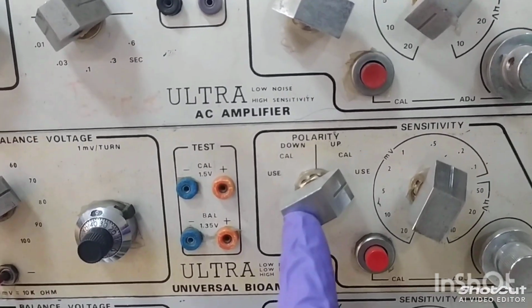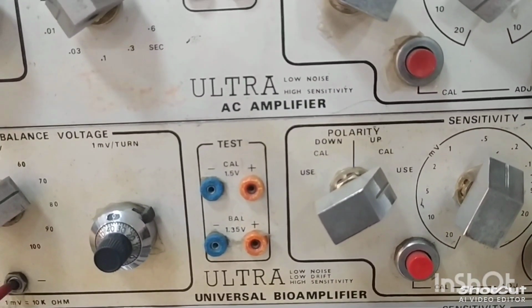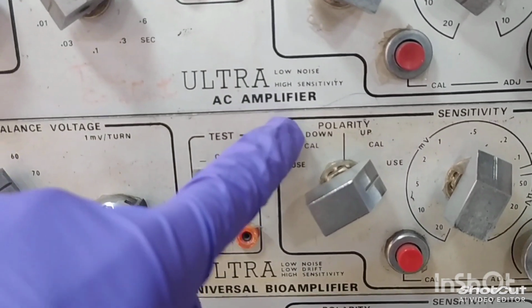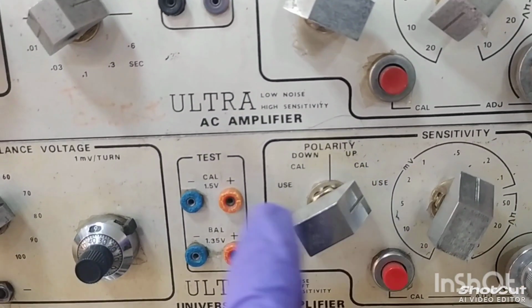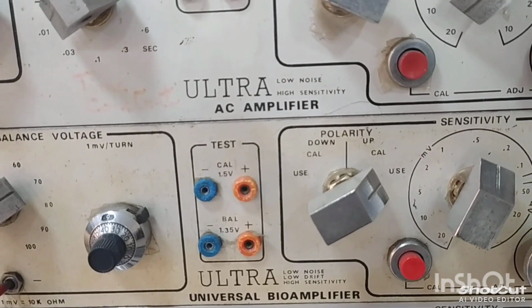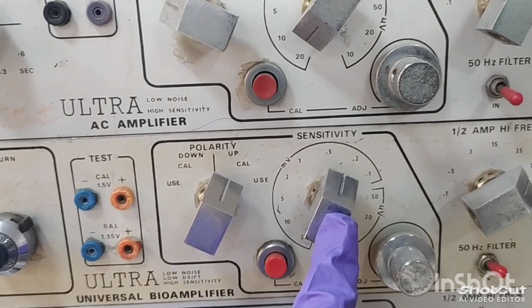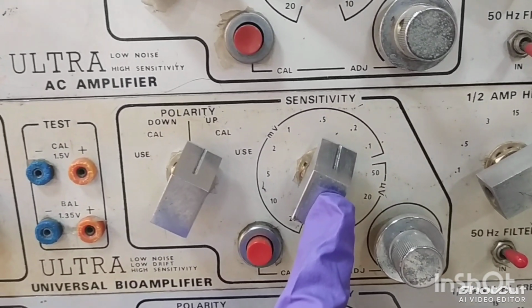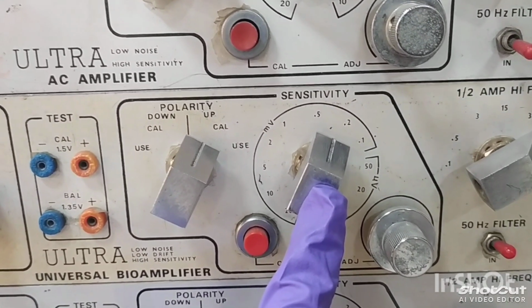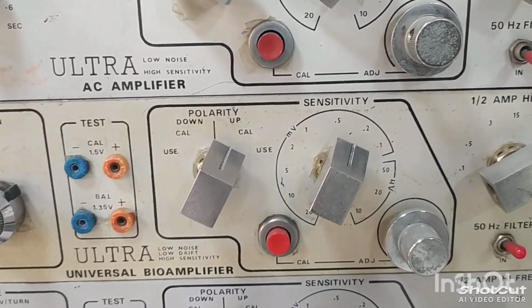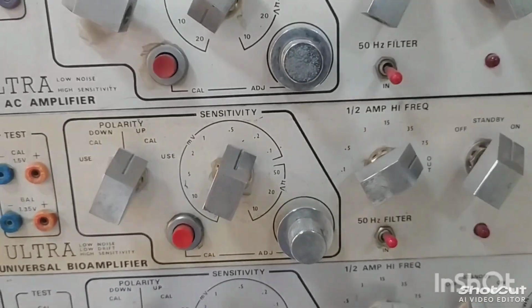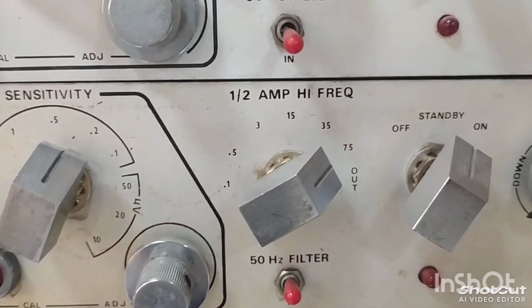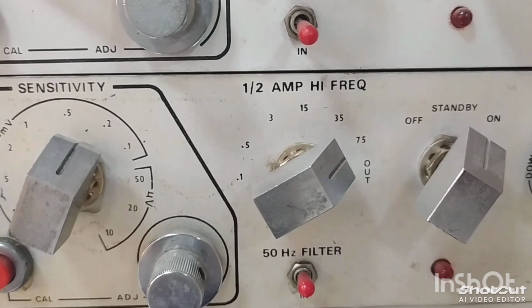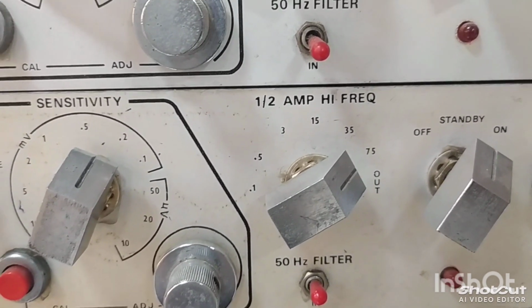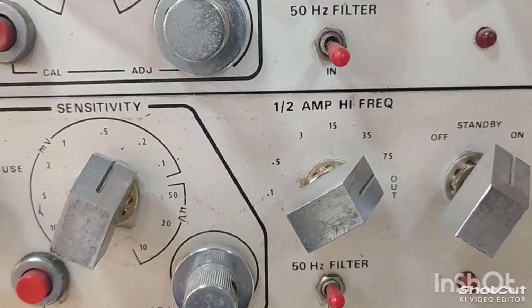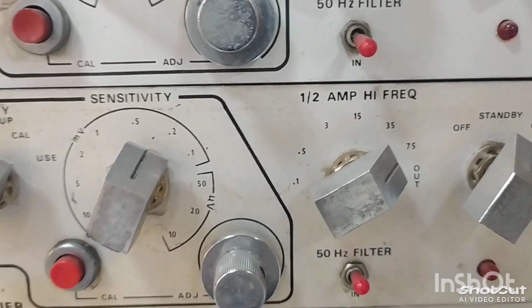Next one is the polarity button. On the polarity button we see written here: down, up, down, up. This is the sensitivity switch, and we need to select the 0.2 millivolt sensitivity. And this is the half amplifier high frequency, which is used to remove the harmonics.